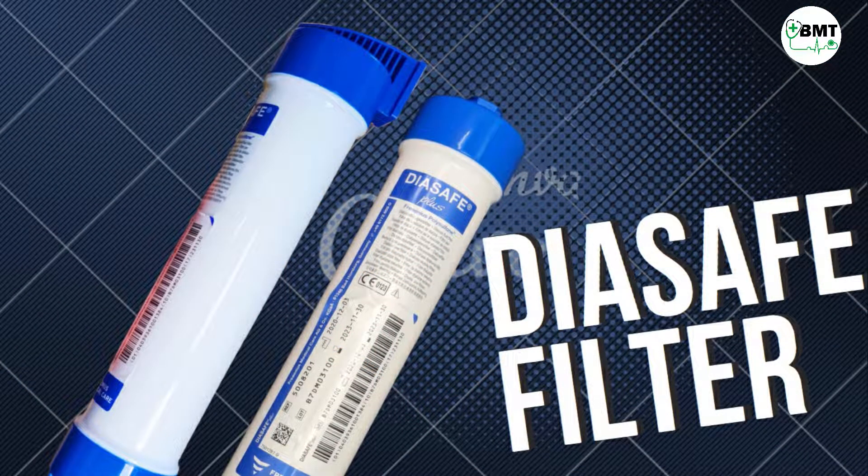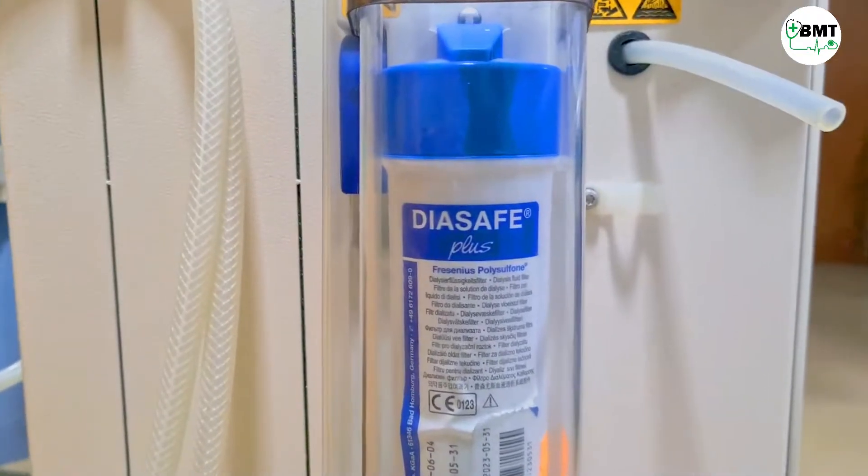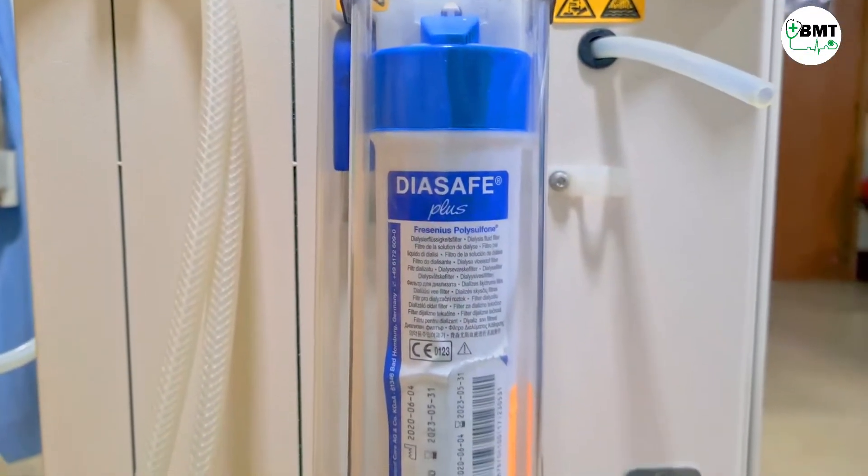Hello friends, today we will be discussing about the Diasafe filter of the Fresenius dialysis machine. In this machine, most commonly water error is found and 99% of the time the Diasafe filter needs to be replaced.